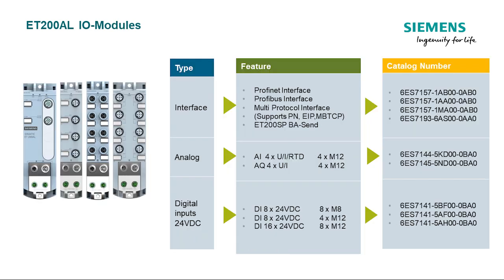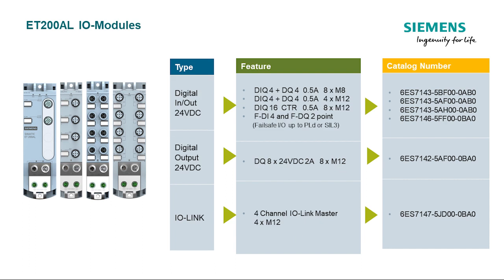Let's look at the selection of I/O modules available. Interface modules can be PROFINET, PROFIBUS, Multifieldbus — that's PROFINET, EtherNIP, or Modbus TCP — or the BA-Send terminal used on the ET200SP. I/O types include analog, digital in, and digital in/out. One specific module to note is the 16 DI/DO module that will support up to four counters at up to 2kHz.